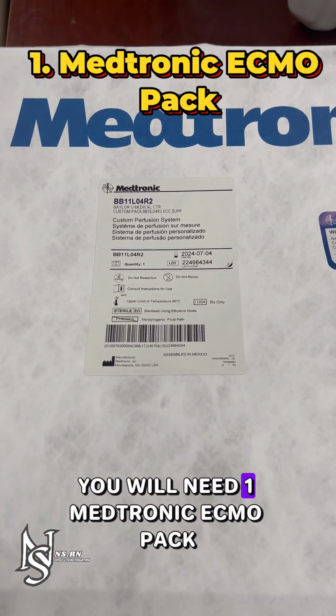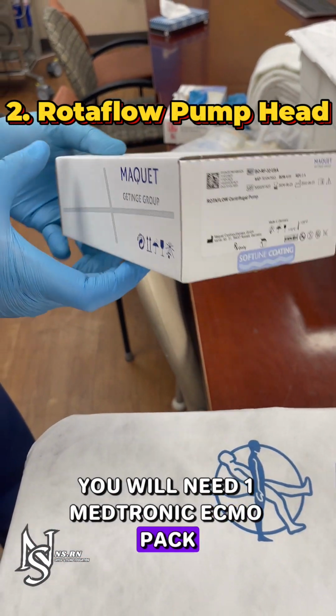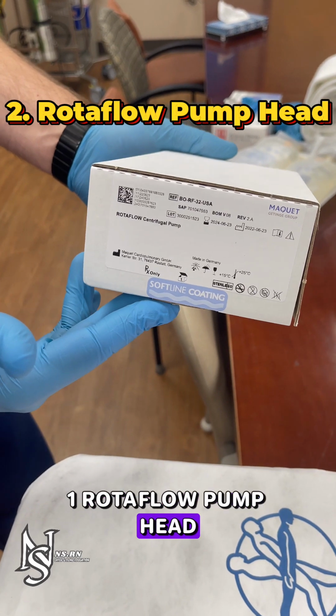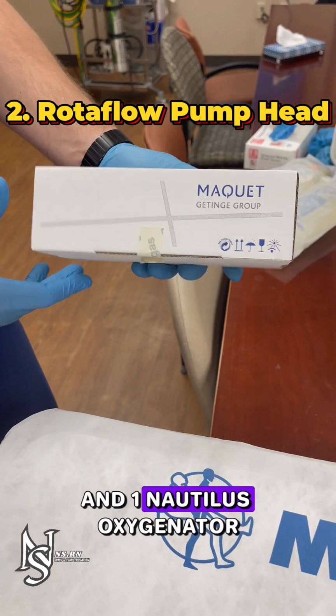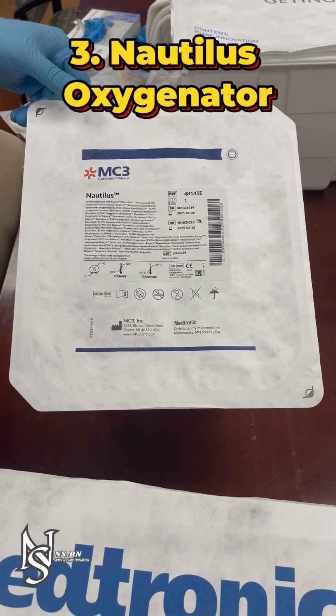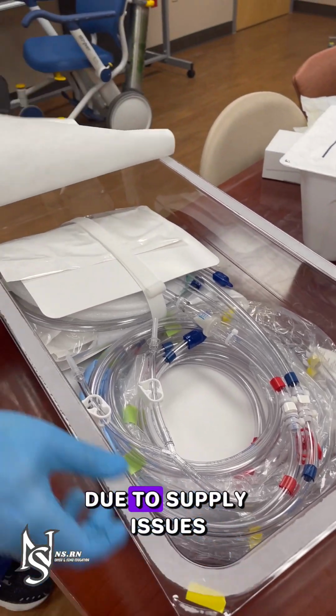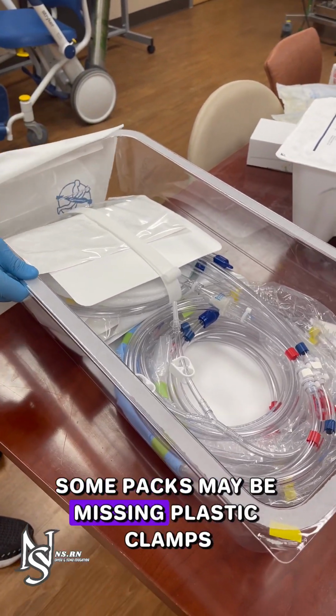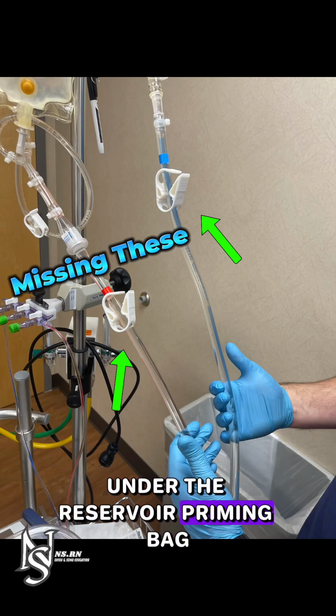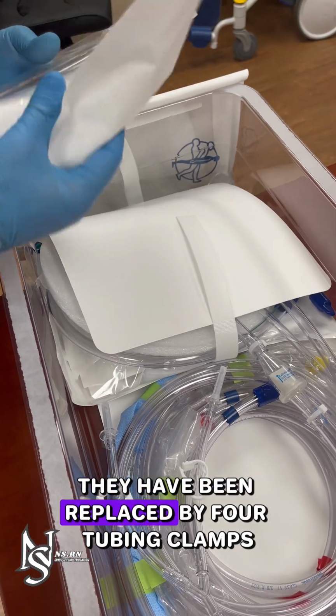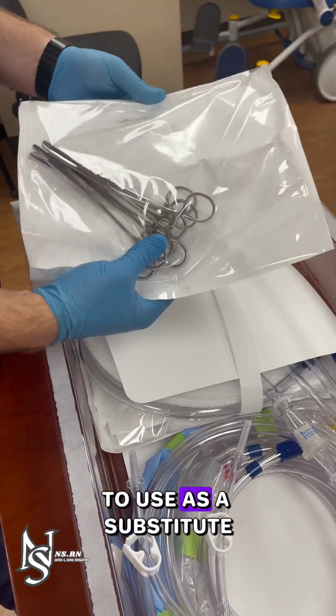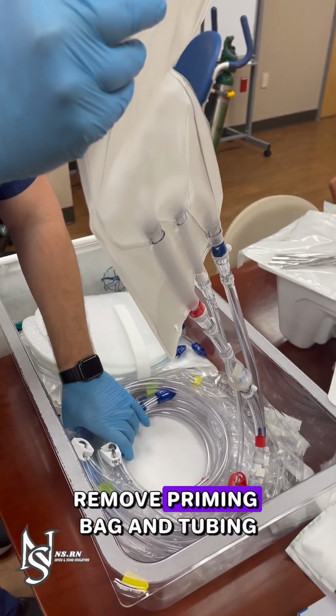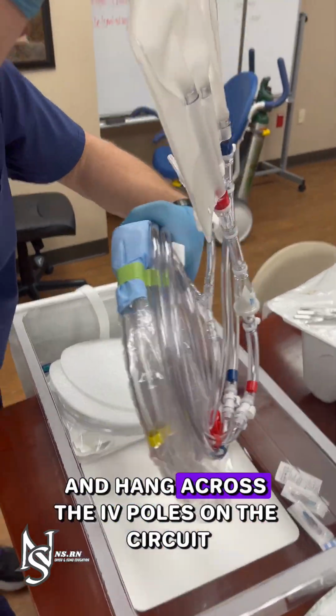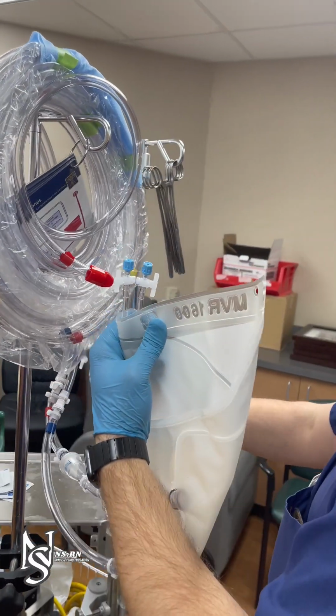You will need one Medtronic ECMO pack, one Rotaflow Pump Head, and one Nautilus Oxygenator. Open ECMO pack. Due to supply issues, some packs may be missing plastic clamps under the reservoir priming bag. They have been replaced by 4 tubing clamps to use as a substitute. Remove priming bag and tubing and hang across the IV poles on the circuit.